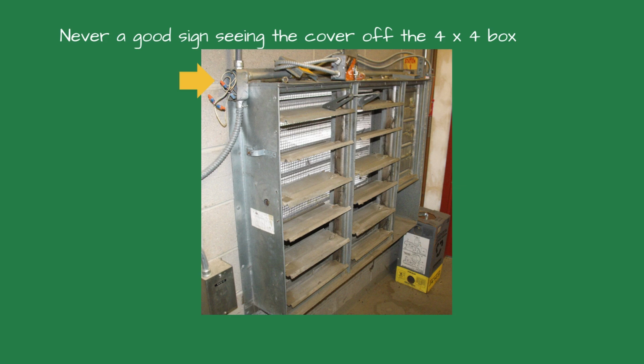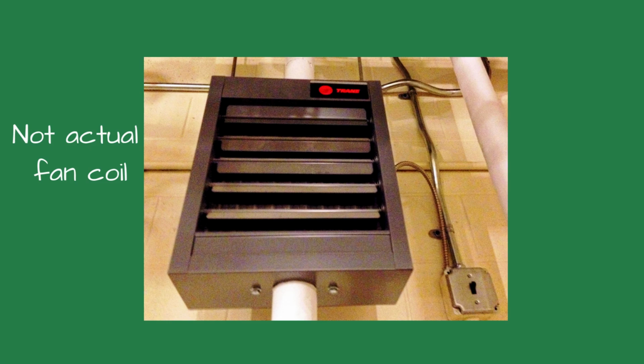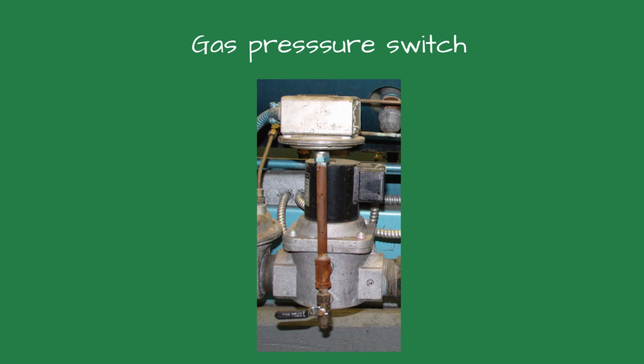At another building, the room had a single gas steam boiler and a steam fan coil unit to heat the boiler room. The fan coil unit was connected to a wall-mounted thermostat. This worked well for decades until the perfect conditions aligned. The outdoor temperature dropped rapidly, and the boiler tripped on the low gas pressure switch. The room had fixed combustion air louvers, and when the temperature dropped to a single digit, the boiler room had no heat. Several pipes froze and sprayed water everywhere.